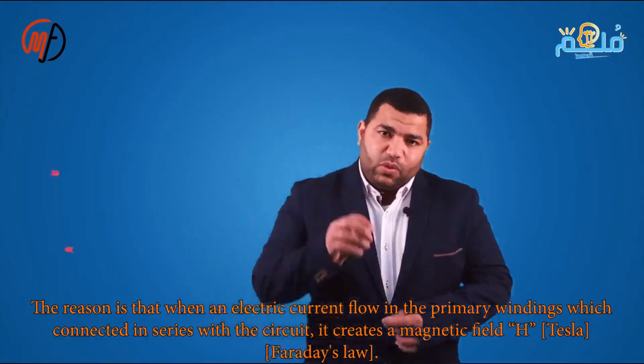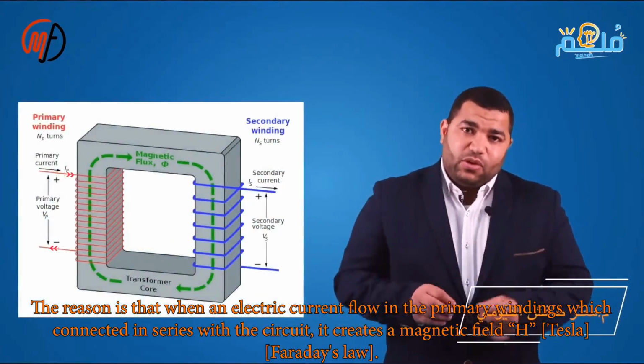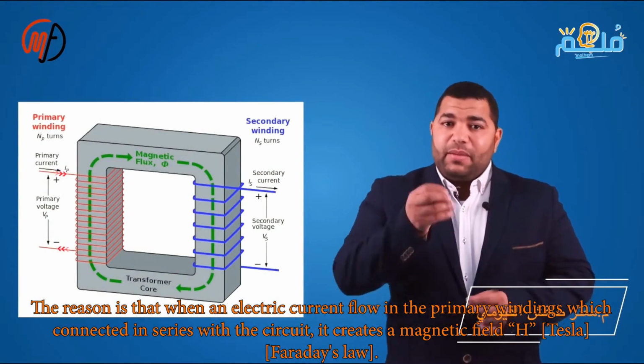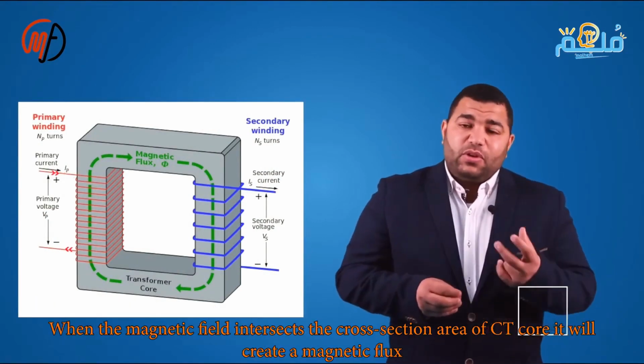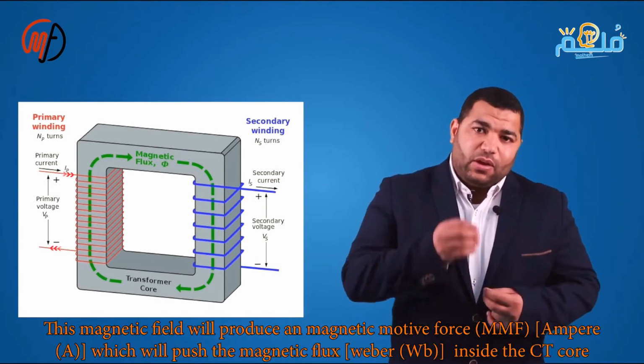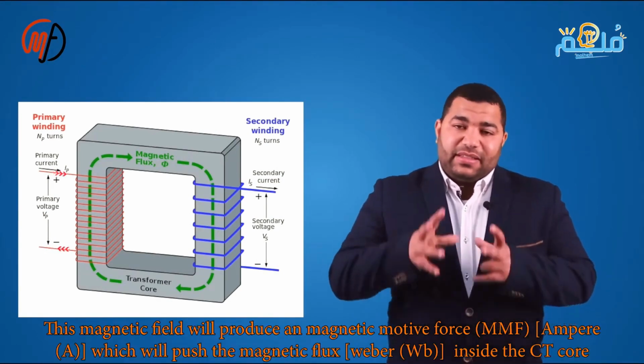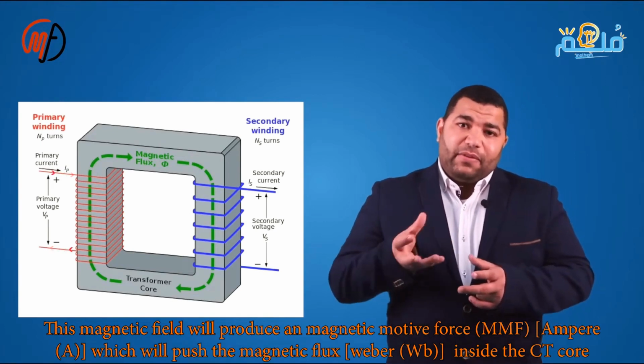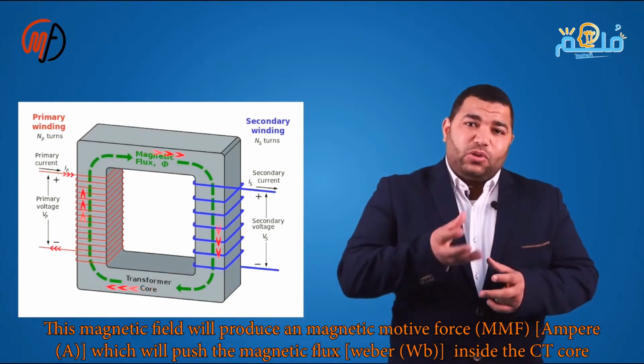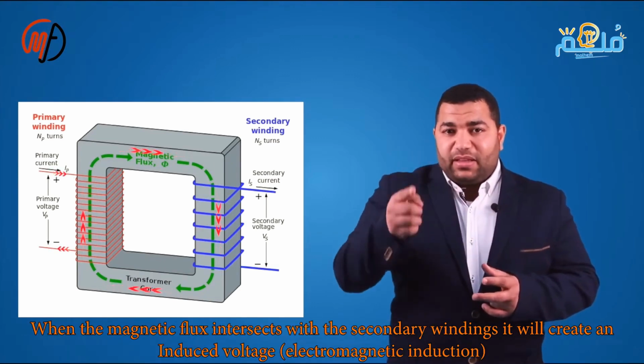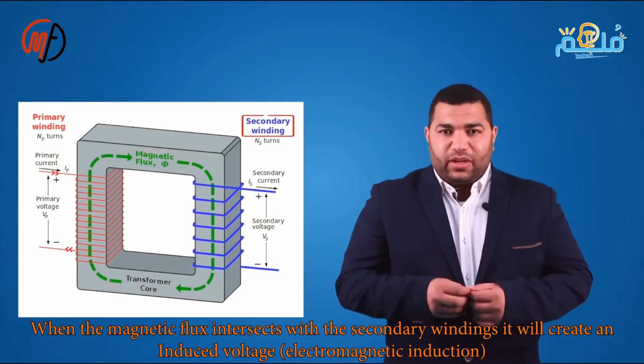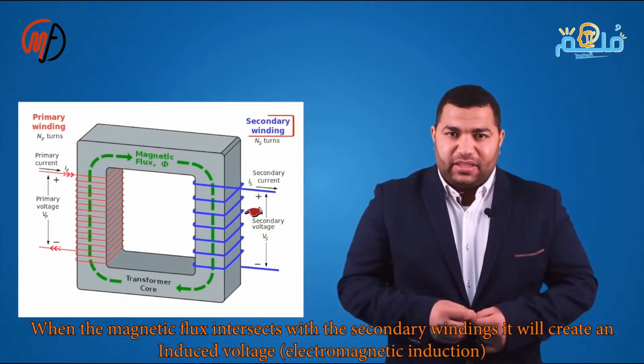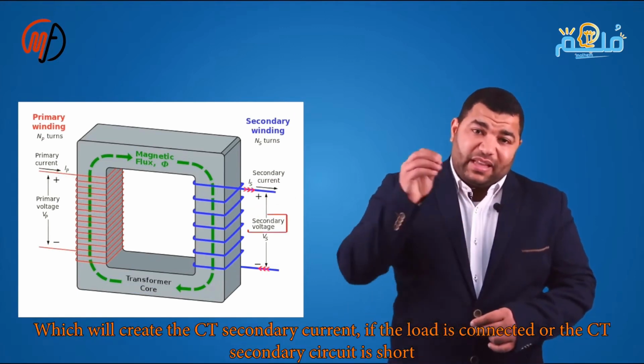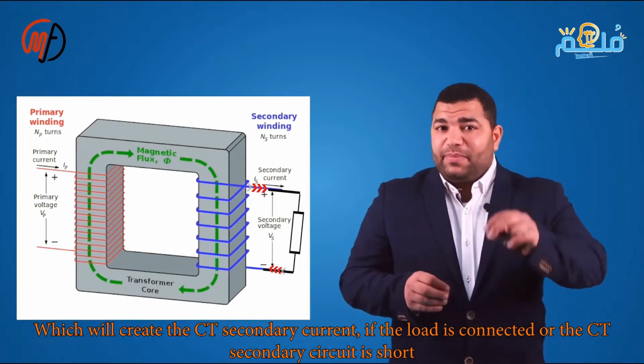When the primary current flows through the CT, it creates a magnetic field, generating a magnetic motive force that pushes the flux into the core. The flux flows within the core, intersects with the secondary winding, and creates voltage and current in the secondary. This creates a new magnetic field opposite to the existing one, reducing its value. If the circuit opens, there's no opposing force, so the original current concentrates in the core, significantly increasing voltage across the terminals. This high voltage is dangerous for the transformer and maintenance workers.